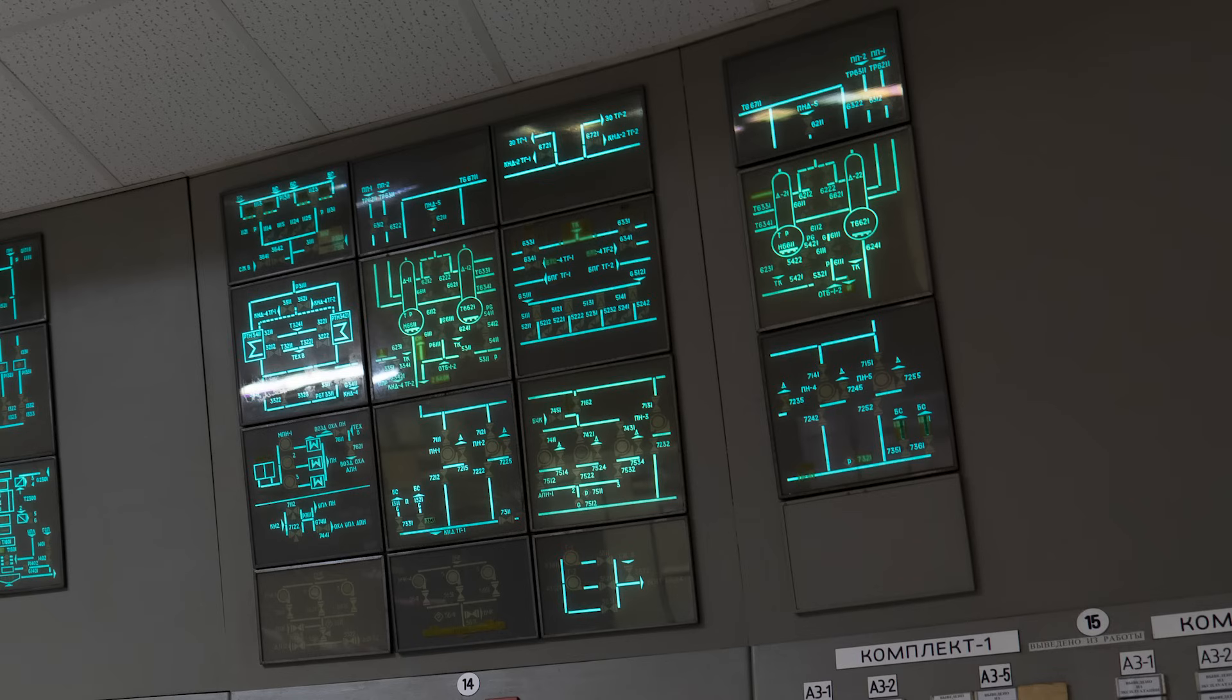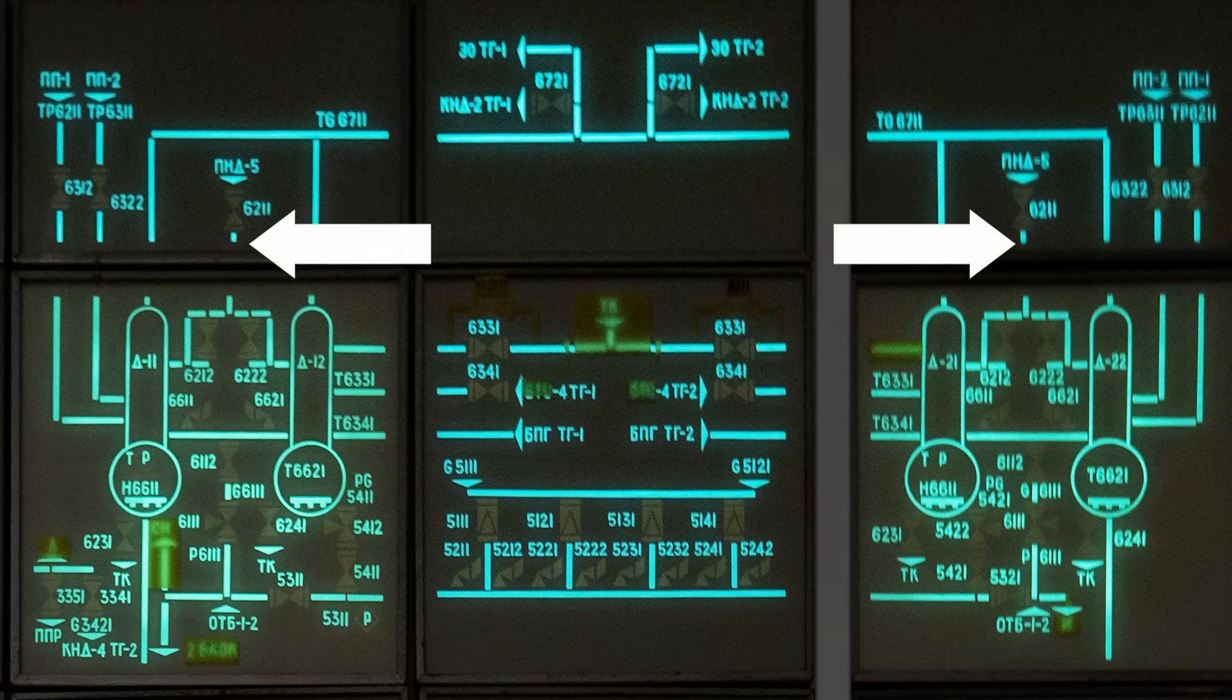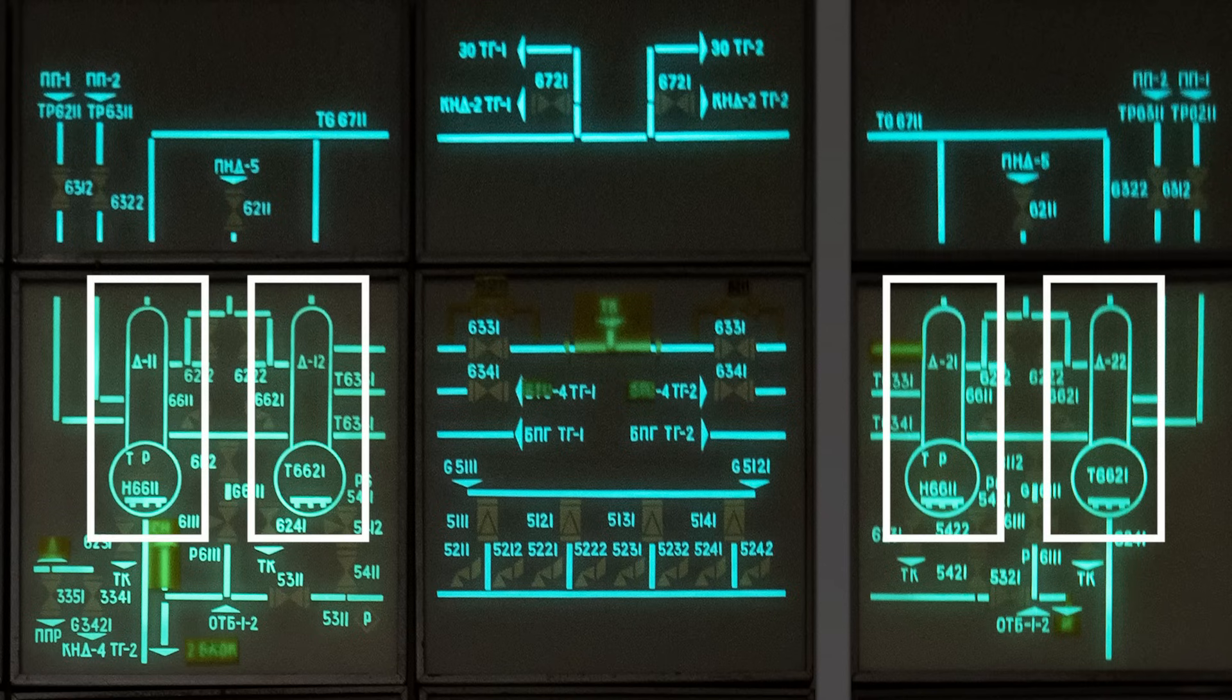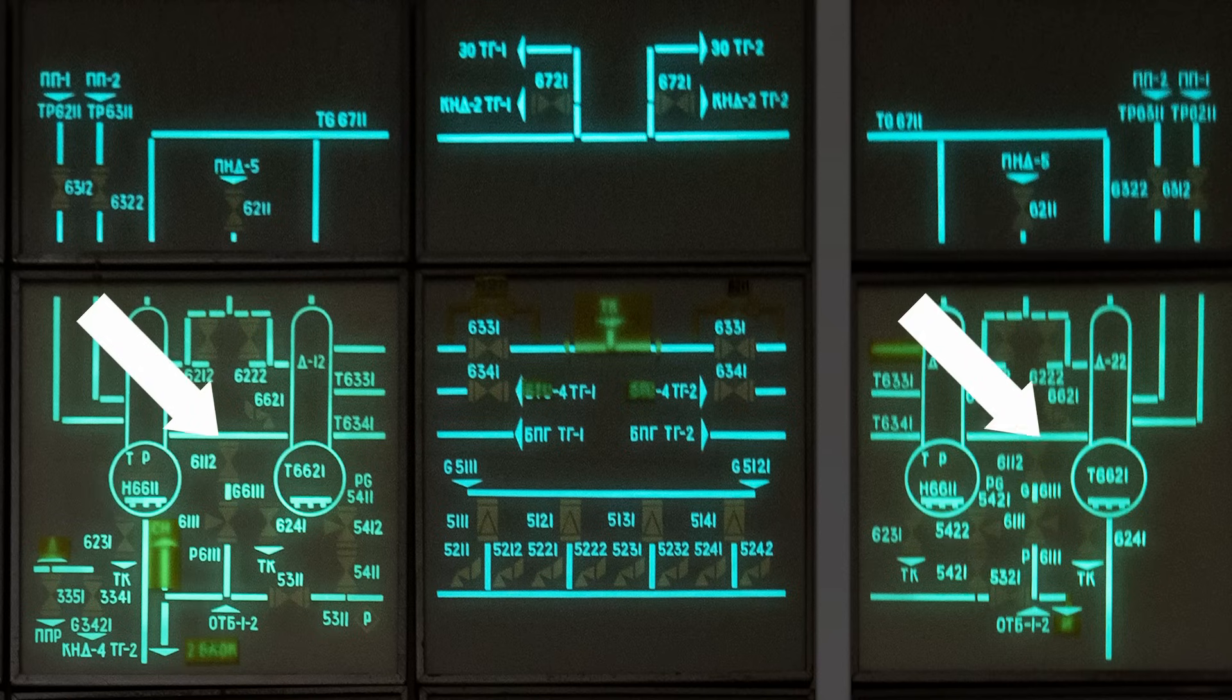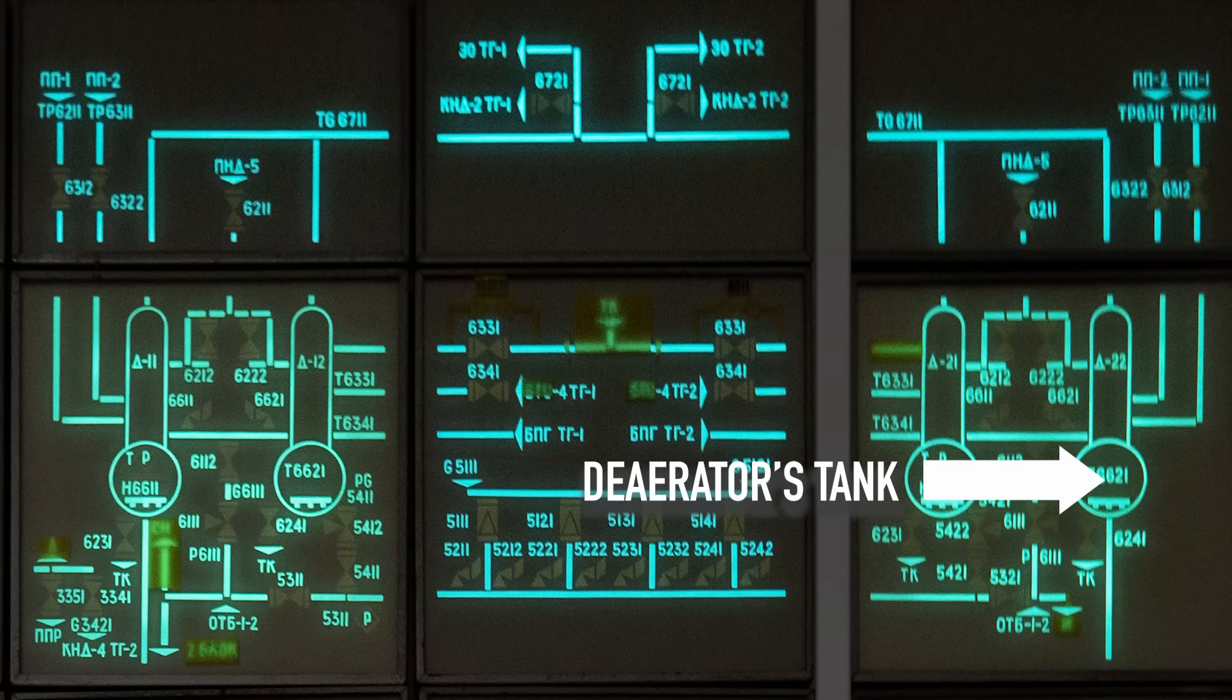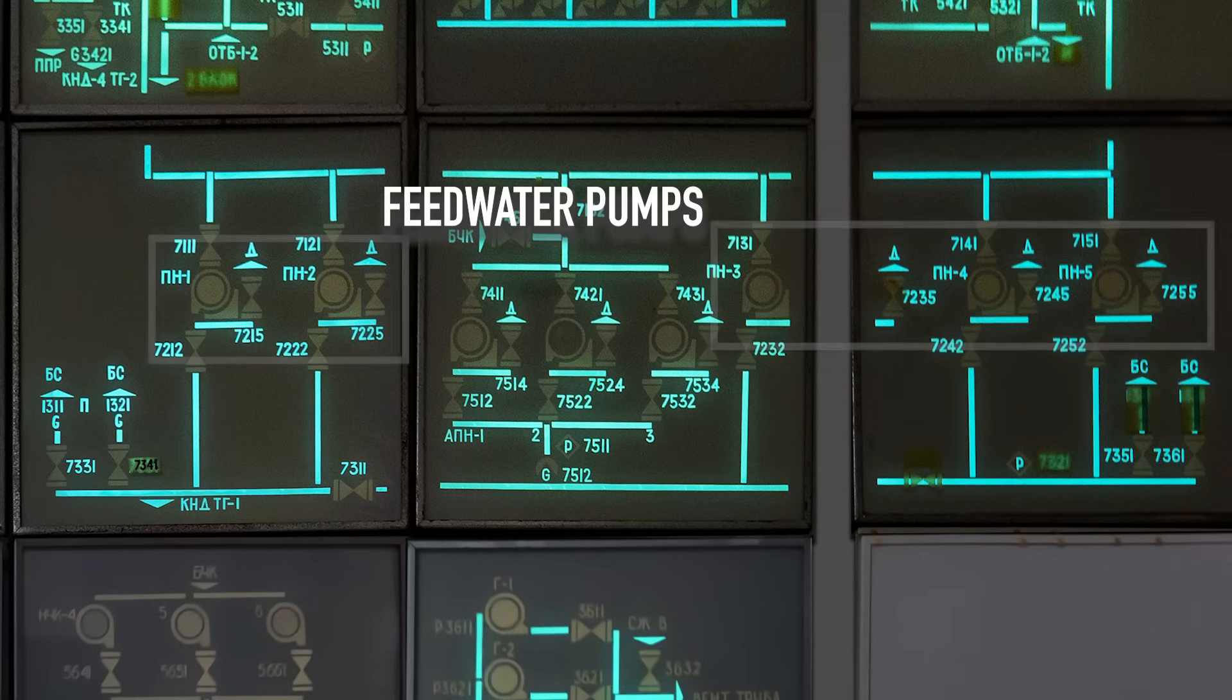Ok, now let's take a look at this display we previously skipped, so this is where comes the turbine condensate. But there is a little problem with it. On its long way it picks up gases like air through microscopic gaps and bolted connections of pipes and valves. There also may appear some CO2. These gases are corrosive and must be removed, and it happens in these devices called deaerators. Inside the deaerator is injected low-pressure steam. It comes either from a turbine exhaust or, during startup, from its intake. The steam mixes with condensate and heats us nearly to the boiling. That process drives out dissolved gases, which are then vented away. And the result is clean feedwater, exactly what we need. The feedwater collects in the deaerator tank and then using these five feedwater pumps is returning to drum separators. And the big cycle starts again.